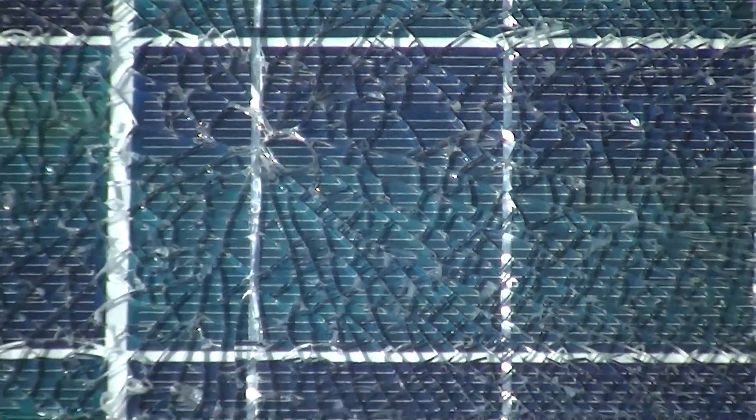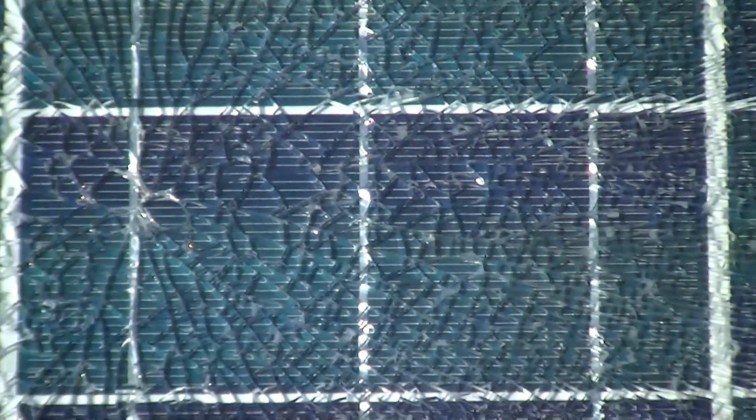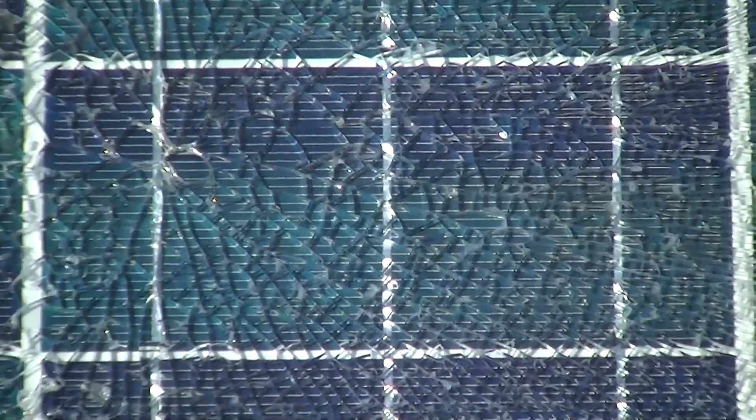I'm going to pull out a little bit so you can see that a little bit better. You can see that that solar cell looks like it got hot right on the busbar and shattered the glass, and that butterfly effect is a very well-known effect in solar modules.